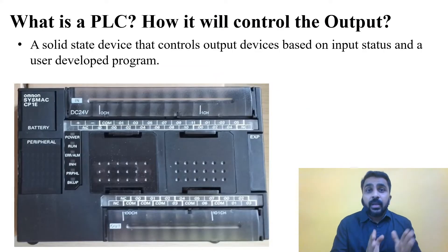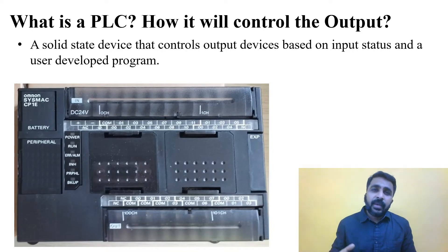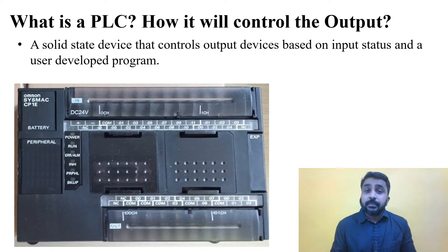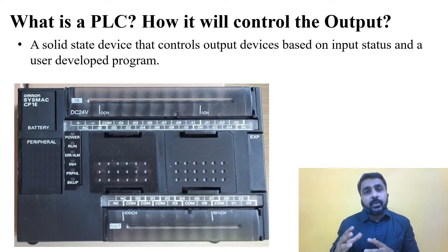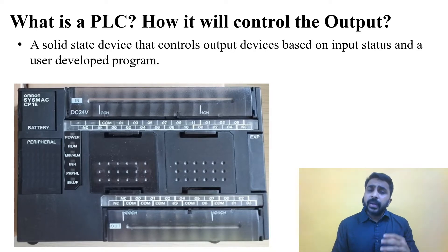Today's topic is: what is a PLC and how does it control the output? The outputs can be a motor, blower, or any 230-volt appliance — sometimes a three-phase motor as well. The PLC gives output at 24 volts, so using 24 volts, we cannot directly control 230-volt motors.